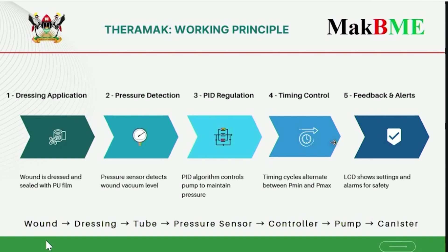So to use the device, the wound is first cleaned and dressed with sterile gauze, and then sealed with polyurethane film to create an airtight seal around the wound area. So after the values and durations of the maximum and minimum pressure have been set, the pressure sensor detects the wound vacuum level and informs the algorithm to control the pump in order to maintain the set pressure. So the timing cycles will alternate between the minimum pressure and the maximum pressure. So in the end, exudate will be drawn from the wound through the silicone tubing and then drained in the canister.